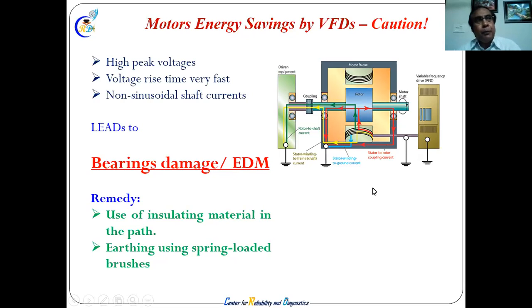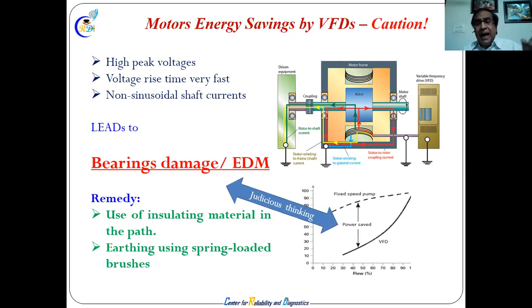Now for the latest motors, if you purchase with VFD, question them how well it is insulated. If insulated, what insulating material is taken? Is the casing a separate material, or is the bearing the material? Will it create an interaction and capacitance or other issues or not? Check, you have to check it. So that is the thing. So you need to have a judicious mixing of your thinking in putting in a VFD.